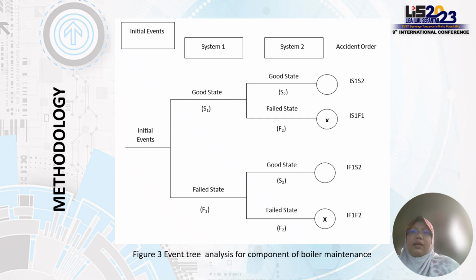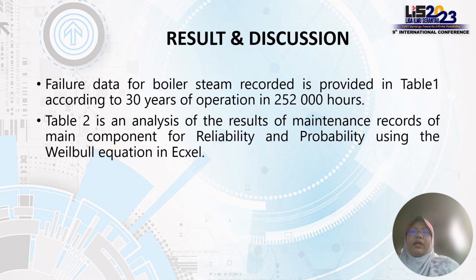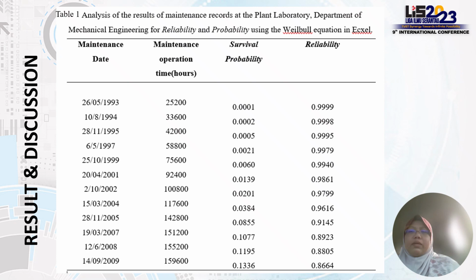For the result and discussion, failure data for the boiler steam recorder is provided in Table 1 according to 30 years of operation, which is 252,000 hours. Table 2 is an analysis of the result of the maintenance record of the main components for reliability and probability using the Weibull equation in Excel. This is part of the data for 30 years in the Polytechnic Plant Laboratory, Department of Mechanical Engineering in the Polytechnic Engku Omar.